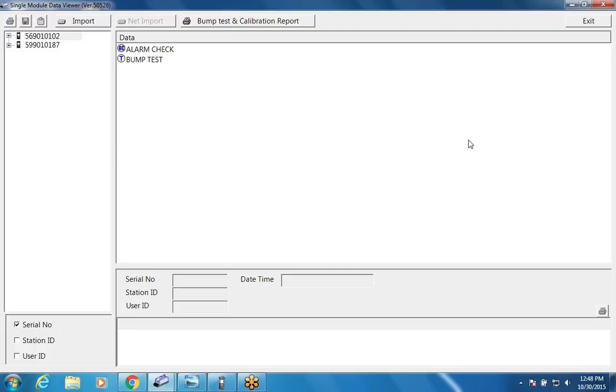If I go into the bump screen, I can set the air time, I can set the gas time, I can set the air purge time, and I can also set the tolerance, which is the accuracy. I can say if I want to do an alarm check or not when I do a bump test, and I can say if I want to automatically print when I do a bump test. So how do you change it? You press the button, and it'll take me to a screen where I can change it. Okay.